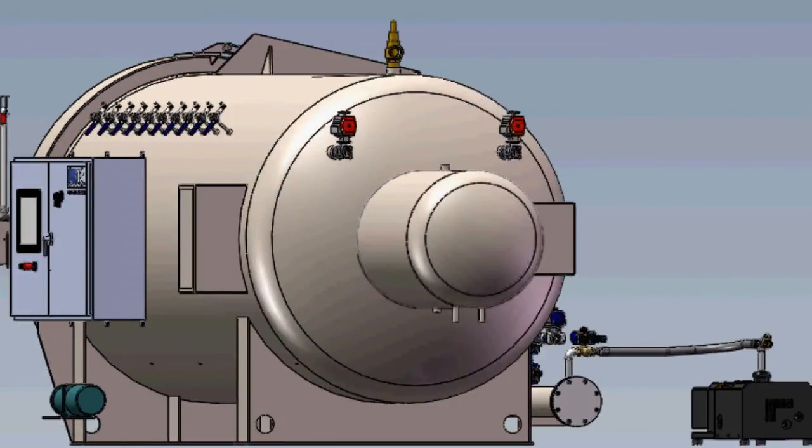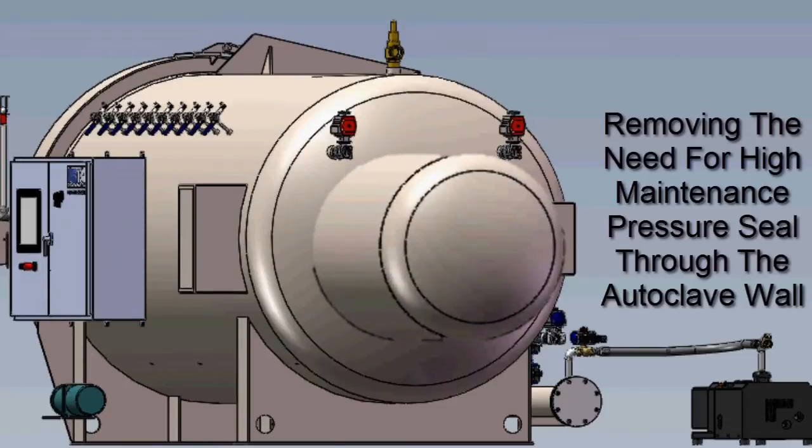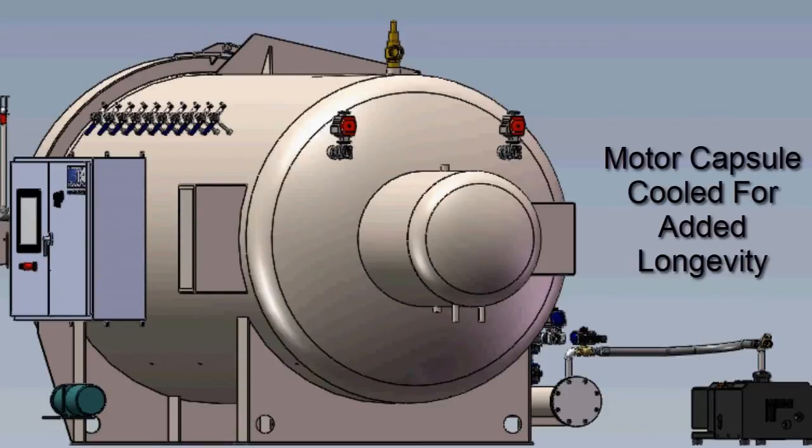The main fan drive motor is enclosed within a pressurized motor capsule. The pressurization of the motor capsule removes the need to have a high-maintenance pressure seal through the wall of the autoclave, thus increasing reliability. The motor capsule is cooled to maintain an acceptable atmosphere for motor longevity and has a removable access cover for ease of maintenance.